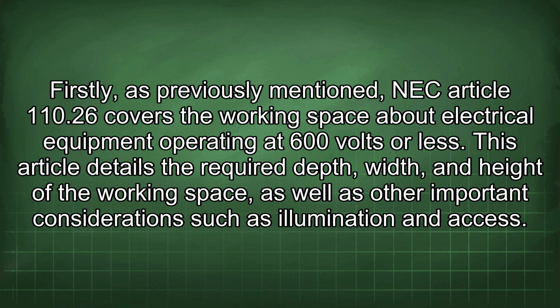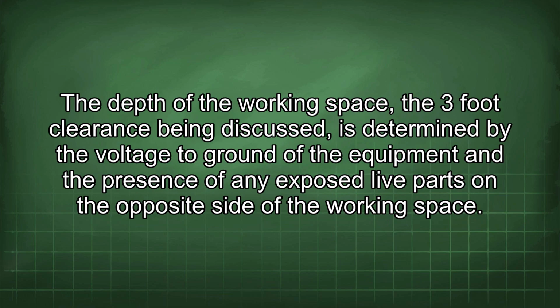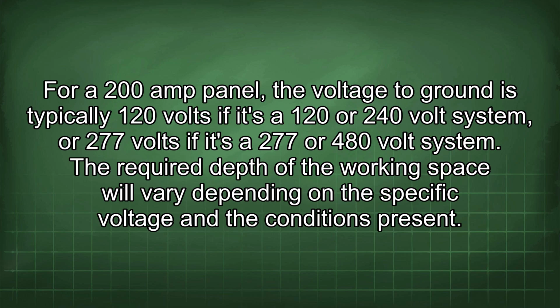as illumination and access. The depth of the working space, the 3-foot clearance being discussed, is determined by the voltage to ground of the equipment and the presence of any exposed live parts on the opposite side of the working space. For a 200 amp panel, the voltage to ground is typically 120 volts if it's a 120 or 240 volt system, or 277 volts if it's a 277 or 480 volt system. The required depth of the working space will vary depending on the specific voltage and the conditions present.